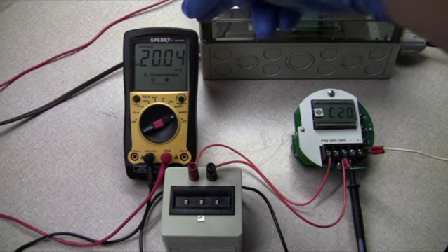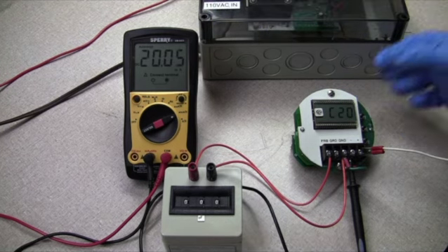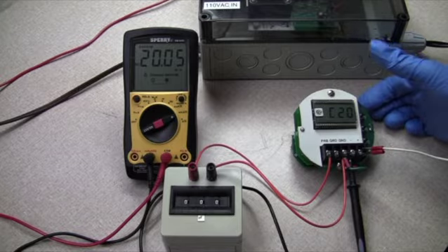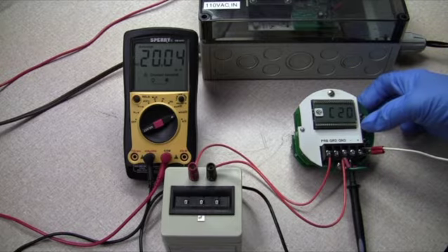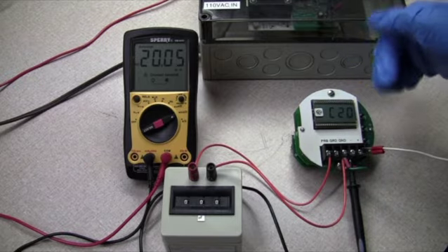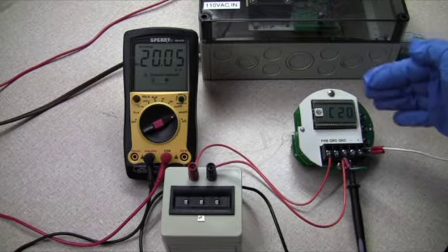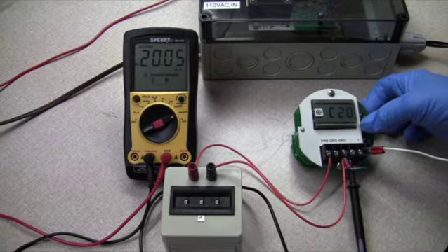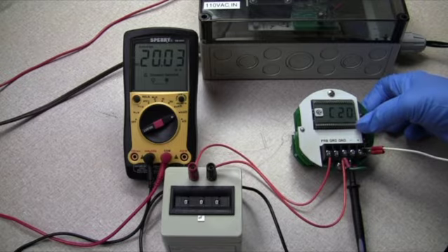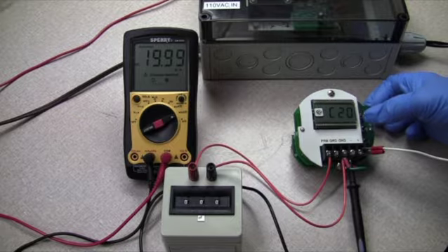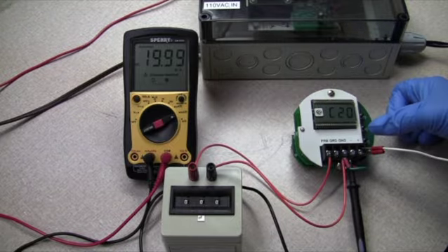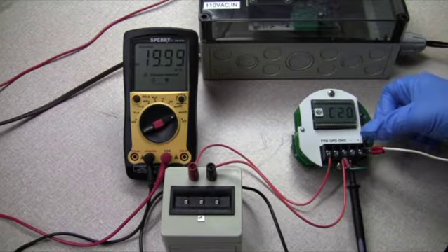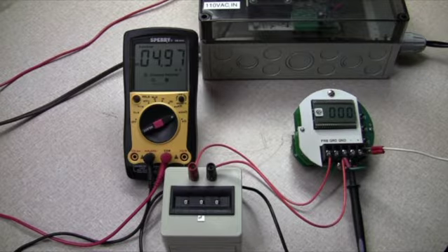So now we can see at 20 milliamps we're off by just a little bit in the hundredths column. The SW2 button is like your downward arrow. The SW1 button is your upward arrow. So we're going to hit this to bring it down just a little bit. Right there. You're at 20 milliamps. Calibration 20. Hit SW3 to enter. And now you're ready to set your high and your low signal.